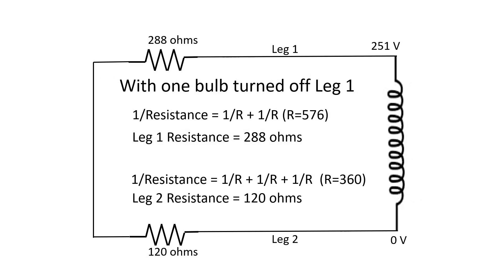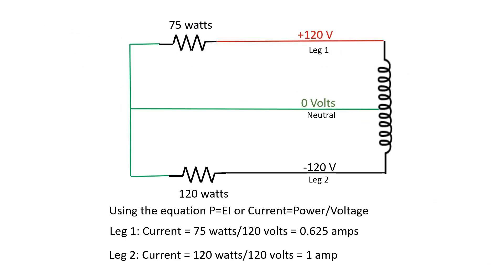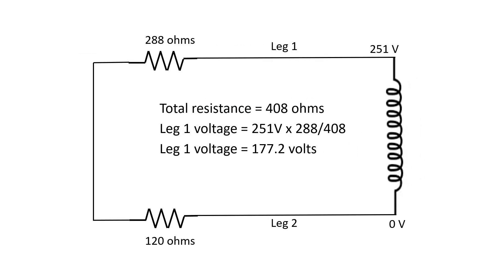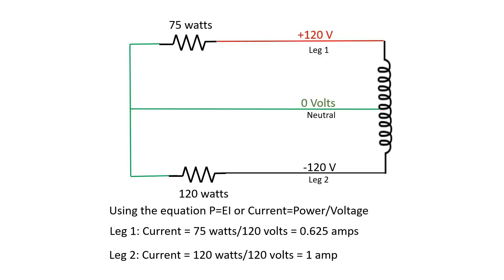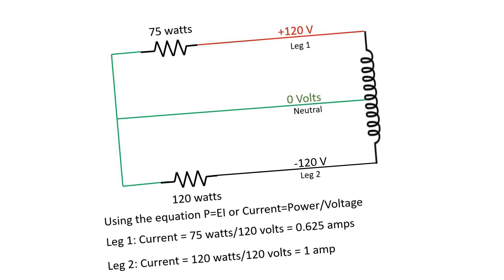I'll work through some calculations using wattage, current, voltage, and resistance to calculate exactly how much voltage you'll have on each leg of an electrical system in the case of a lost neutral. If you know the power consumption of any device, you can use Ohm's Law to calculate exactly how much voltage and resistance that device consumes, and you'll be able to calculate the voltages on each leg.